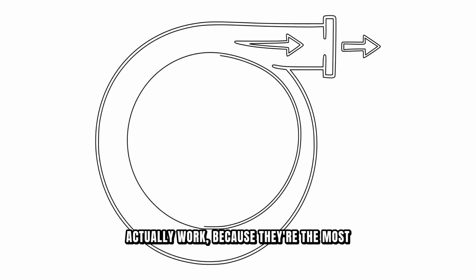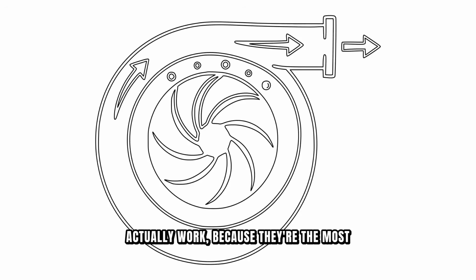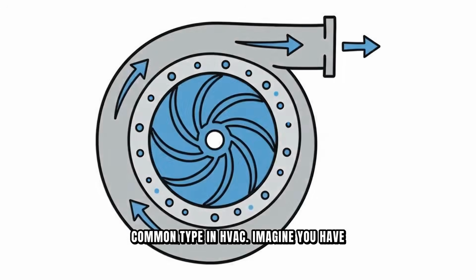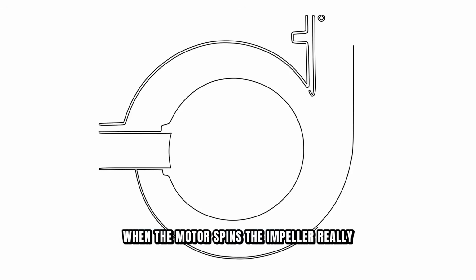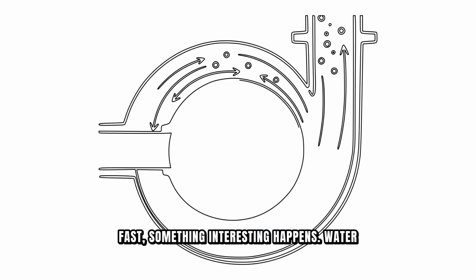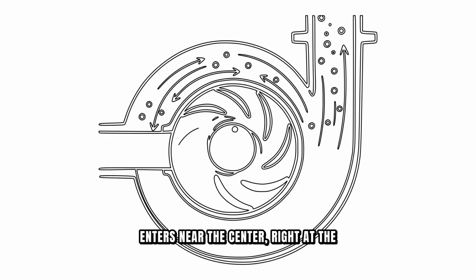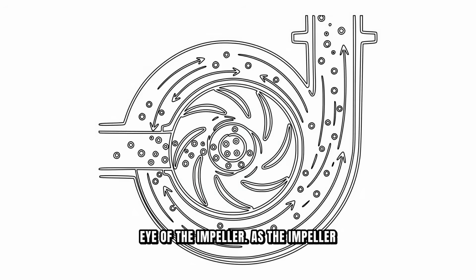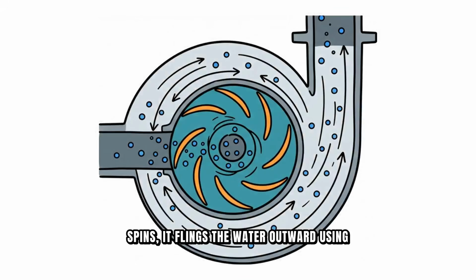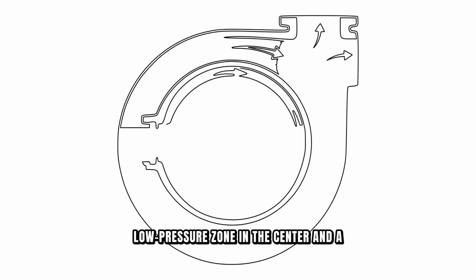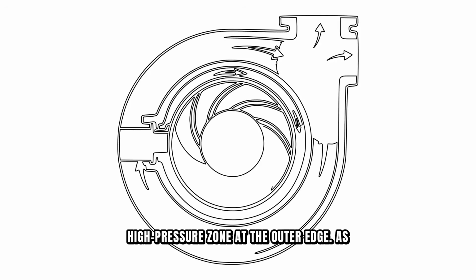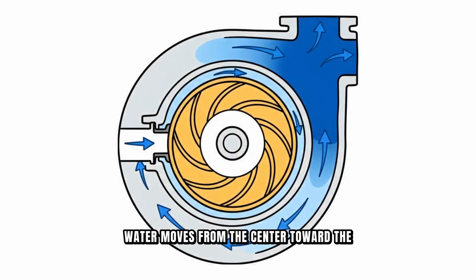Now let's dive into how centrifugal pumps actually work, because they're the most common type in HVAC. Imagine you have a spinning wheel inside a circular chamber. That wheel is called an impeller. When the motor spins the impeller really fast, something interesting happens. Water enters near the center, right at the eye of the impeller. As the impeller spins, it flings the water outward using centrifugal force, kind of like a merry-go-round throwing riders toward the edge. This spinning action creates a low-pressure zone in the center and a high-pressure zone at the outer edge.